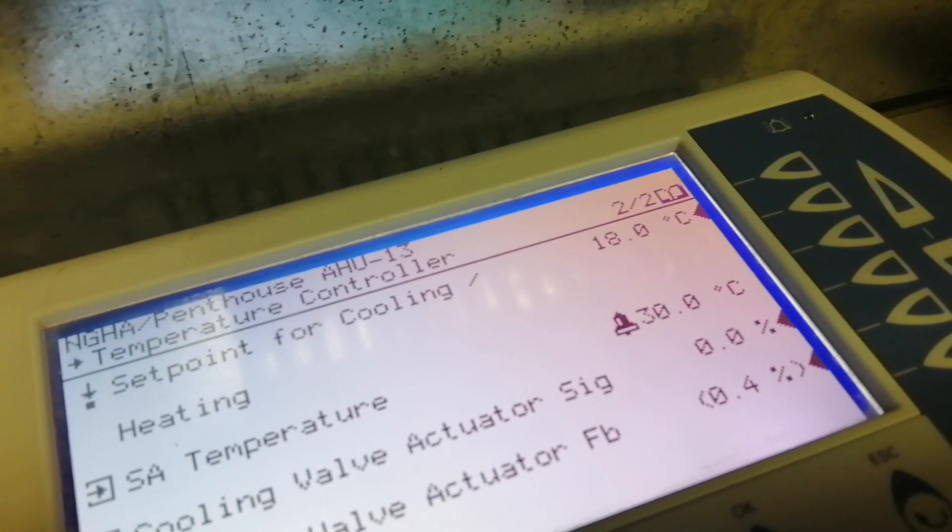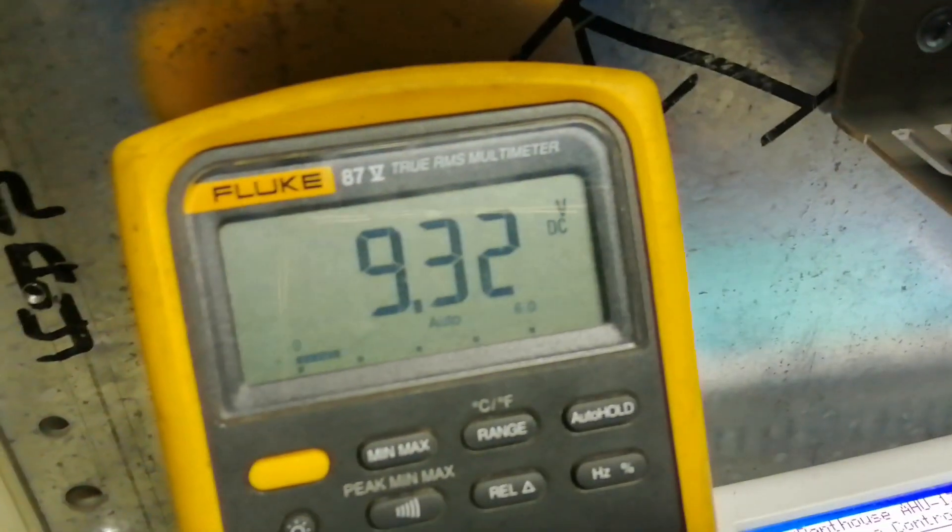Temperature high alarm is activated at 30 degrees centigrade with an equivalent of 9.32 voltage signal.